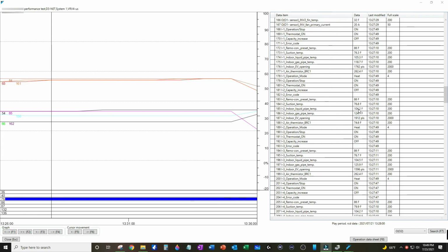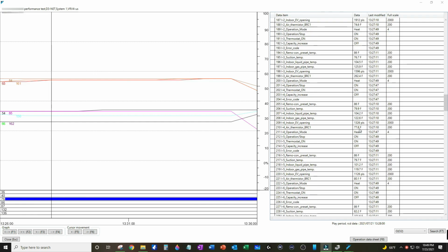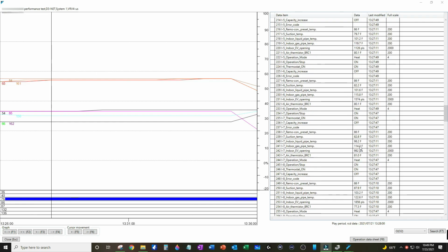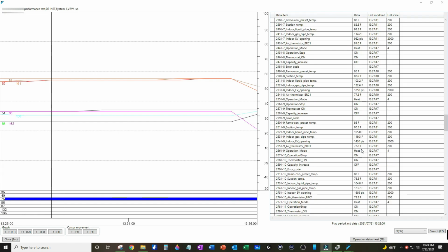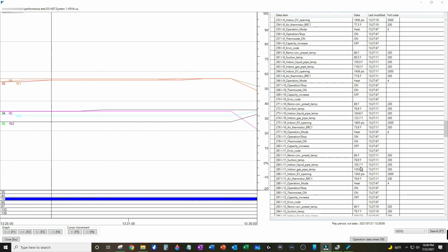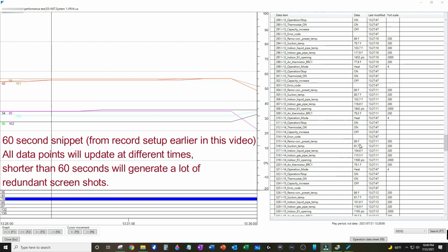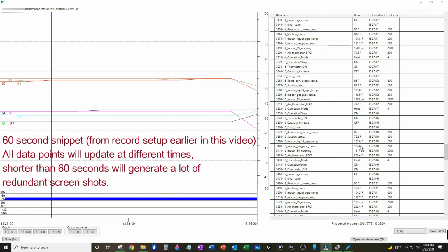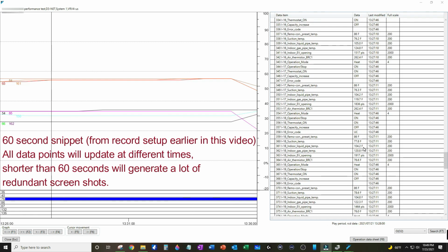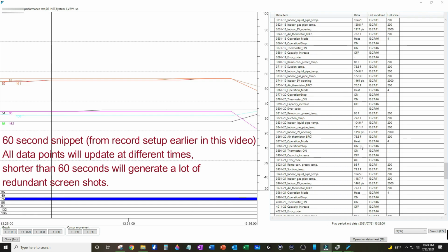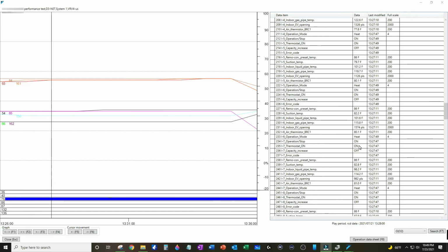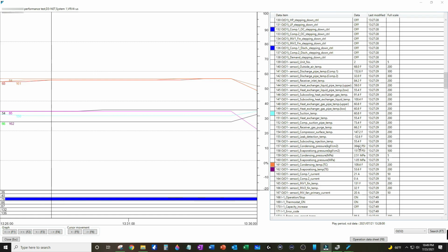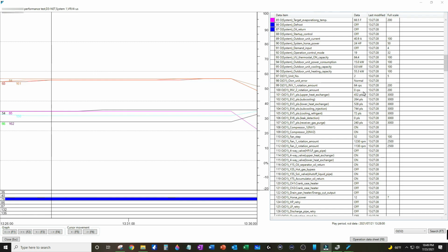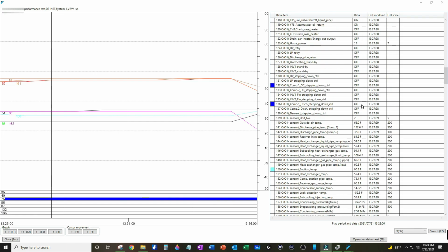Next, I'll scroll down and check subcooling at each indoor unit. 9 or 10 degrees would be optimal, but I'll accept 7 to 16 without really blinking much. I found a few indoor units flirting with low subcool values, but it's important to note that we're looking at screenshots and not live data. So if anything arises that you think is bad, sit on it for a few minutes to make sure it corrects or investigate what could be causing the problem. Coil temps all looked good though, and we had about 100 degree Fahrenheit gas coming back to the condenser outside. So I'll check EEV positions at the outdoor unit and make sure the outdoor is maintaining proper superheat. Everything looks good here as well.